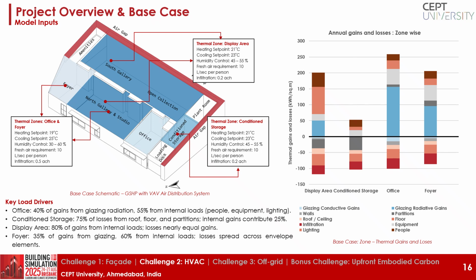The display area is driven mostly by internal gains with nearly 80% of its load from people, lighting and equipment. In contrast, the conditioned storage is heating dominant, requiring stable preservation conditions. The office and foyer are cooling dominant zones with around 40 and 35% of their gains coming from solar radiation through glazing. These differences highlight that a zone-wise HVAC approach is essential to maintain comfort and efficiency across the gallery.